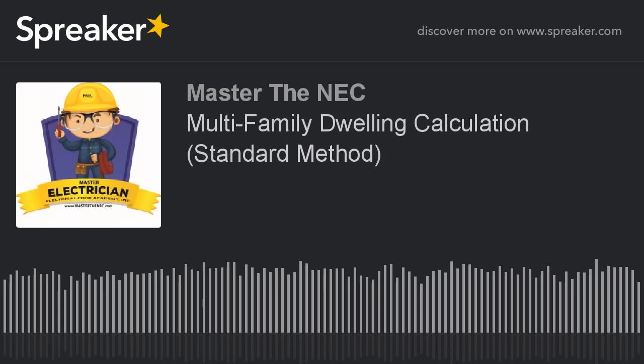So 5,000 watts would be equivalent to 5 kW, or 5 kVA, which would be 5,000 VA. I think you get the point. All right, so it says that the load for a household electric clothes dryer in a dwelling unit shall be either 5,000 watts or VA or the nameplate rating, whichever is larger for each dryer served.